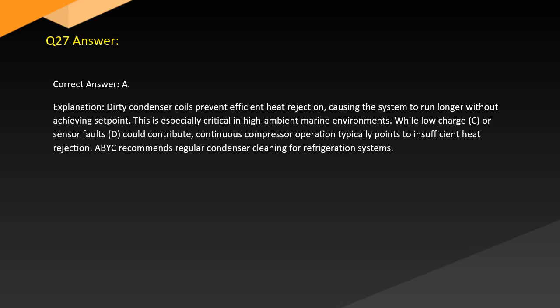Answer. Correct answer: A. Explanation. Dirty condenser coils prevent efficient heat rejection, causing the system to run longer without achieving set point. This is especially critical in high ambient marine environments, while low charge (C) or sensor faults (D) could contribute. Continuous compressor operation typically points to insufficient heat rejection. ABYC recommends regular condenser cleaning for refrigeration systems.